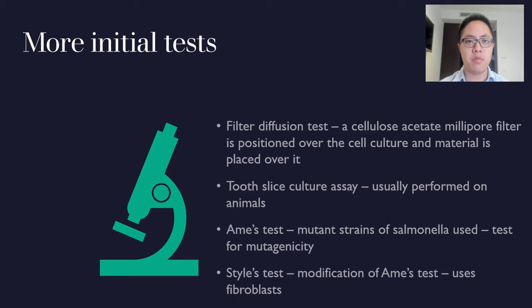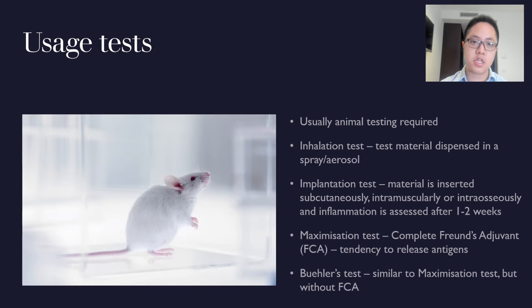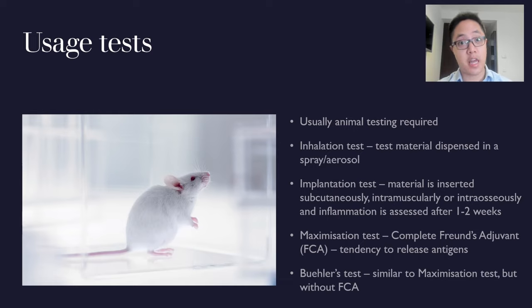Additional initial tests include filter diffusion tests, tooth slice culture assays, AMES tests, and Style's test. There are a lot of tests available. Usage tests generally involve animals — for instance, the inhalation test, where the test material is dispensed as a spray or aerosol and an animal's response is measured. This is the next level of testing compared to initial tests.